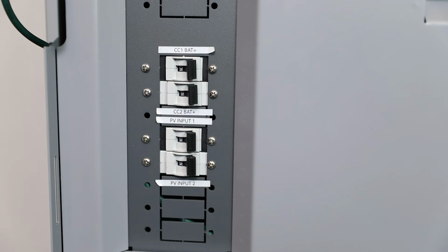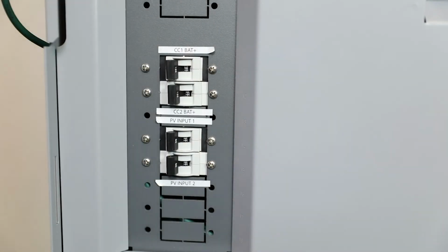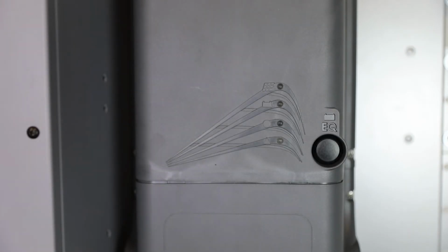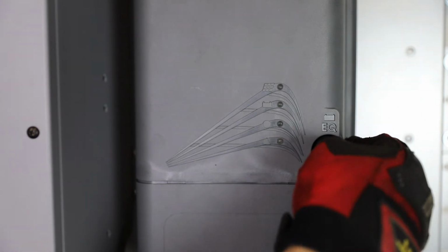All right, to begin, turn off the PV input source breaker, followed by the battery output source breaker. Ensure all LEDs are off. Press and hold the EQ button. While holding, turn back on the battery source breaker.